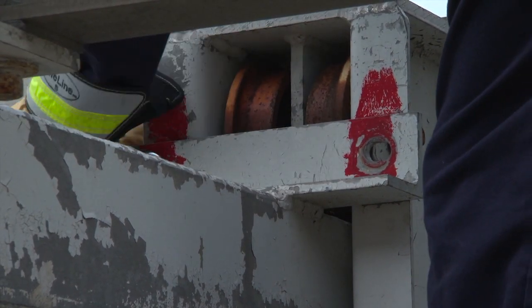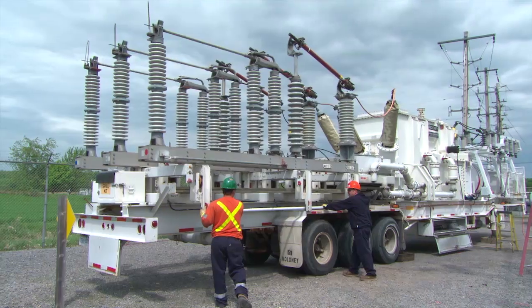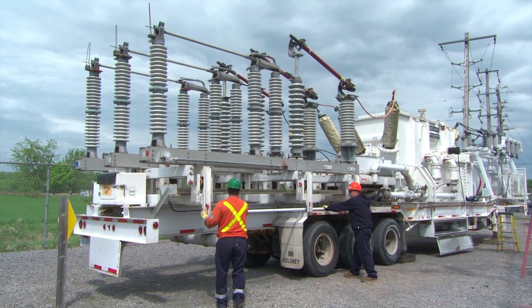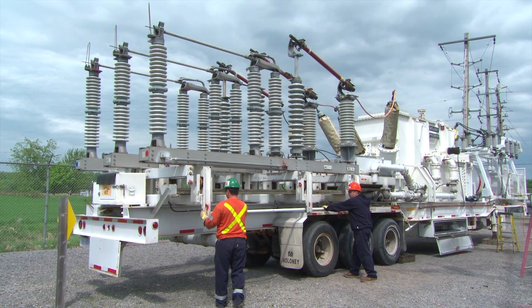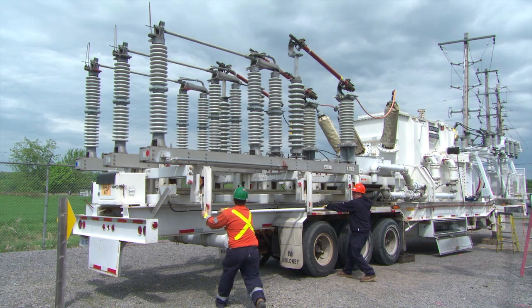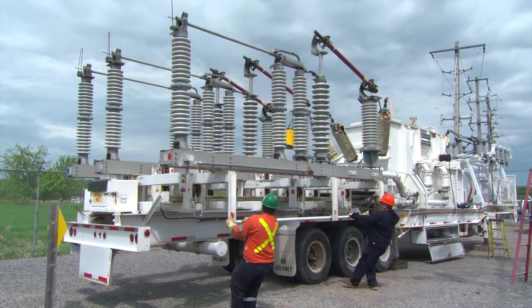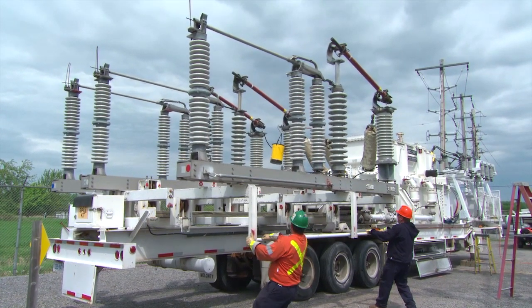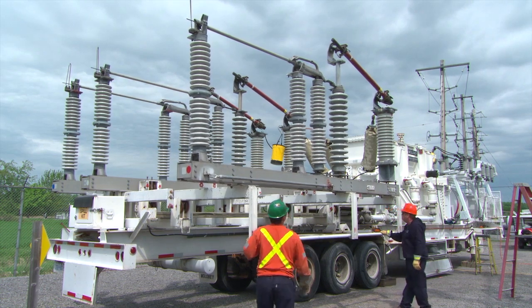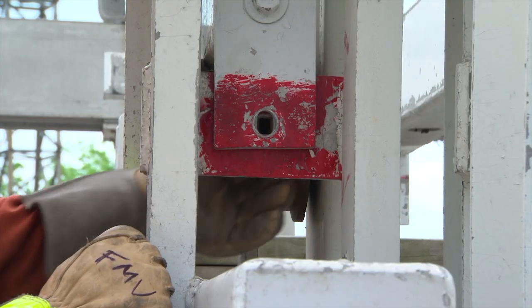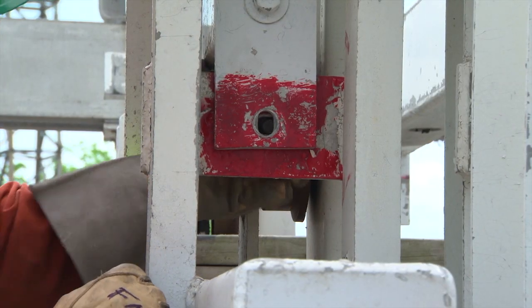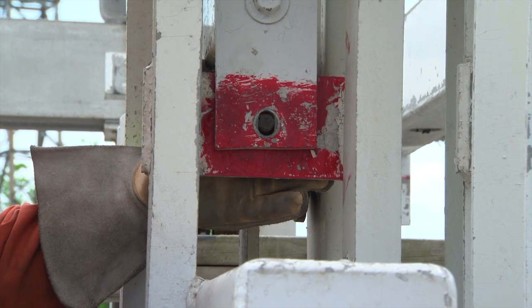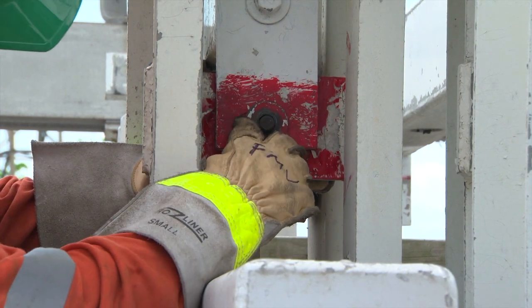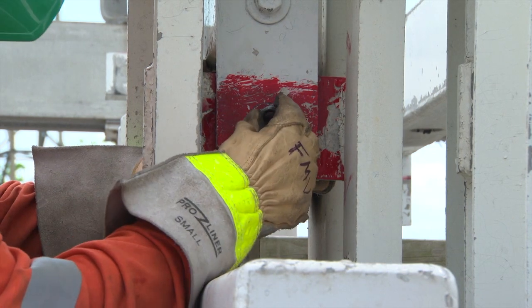Expand the HV switch into its operational position. Remove the 9 transportation bolts to allow for expansion of the high voltage switch. Carefully roll out the switch. Install 3 locking bolts into the anchoring plate to hold the structure in the extended position. Then do the same for the opposite side.